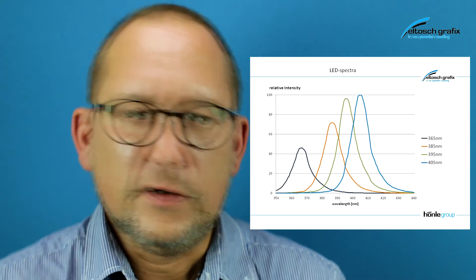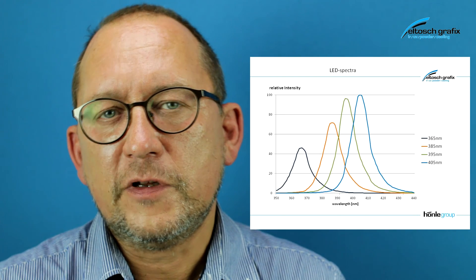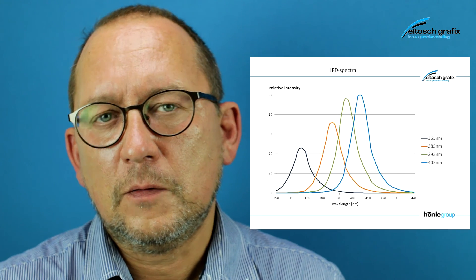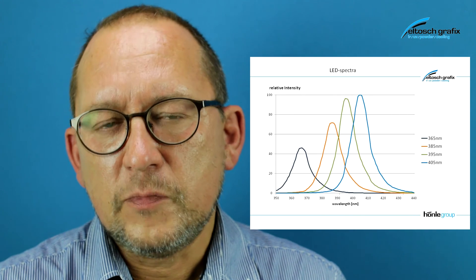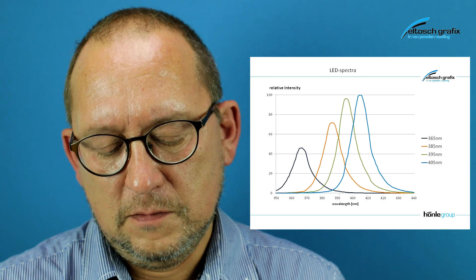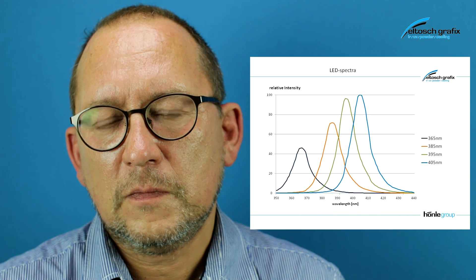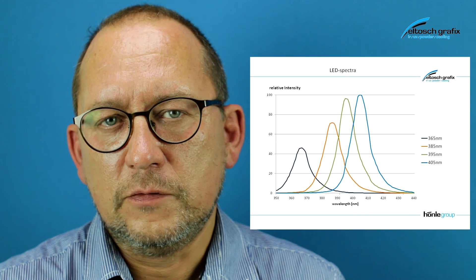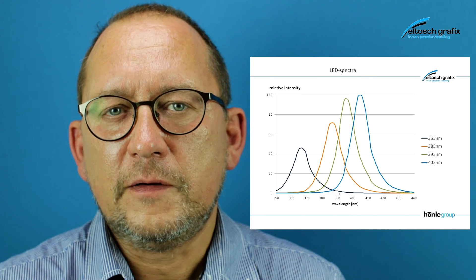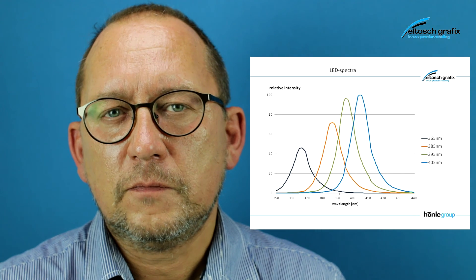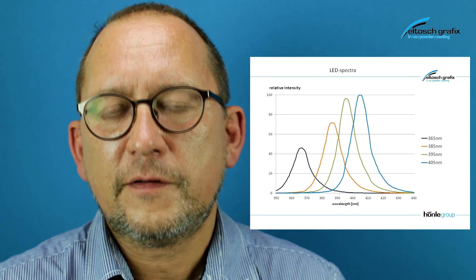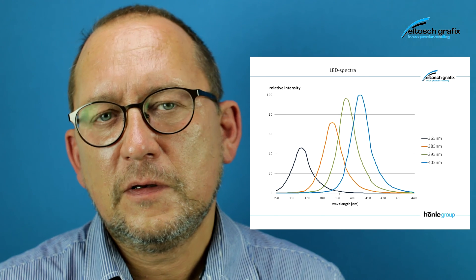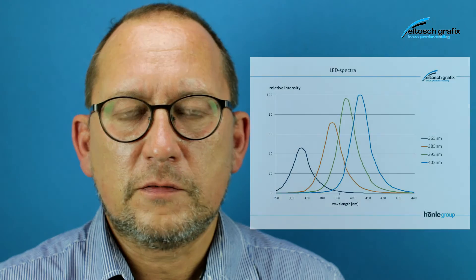As the LEDs only emit a certain wavelength which is in the UVA range, there is also no generation of infrared radiation, which is the case with conventional gas discharge lamps. Another important fact: since the LEDs only work in UVA, they are not generating ozone. Ozone is generated only at wavelengths below 250 nanometers, and LEDs do not generate these wavelengths.